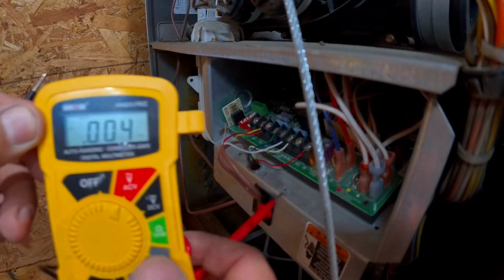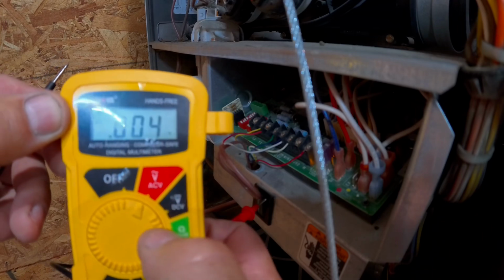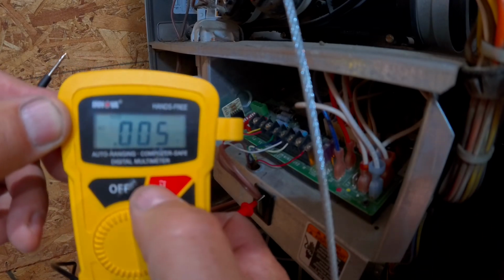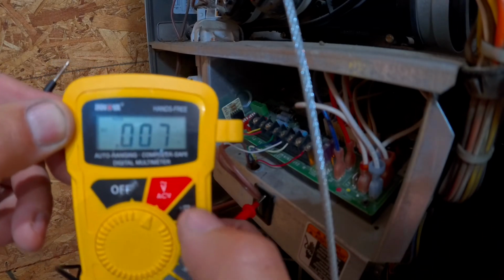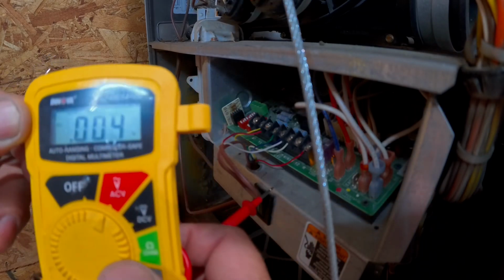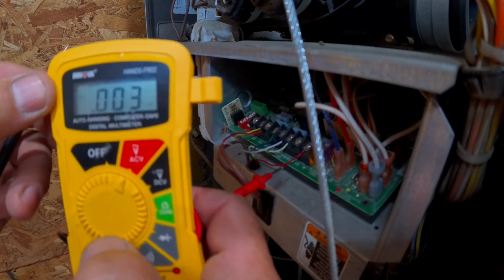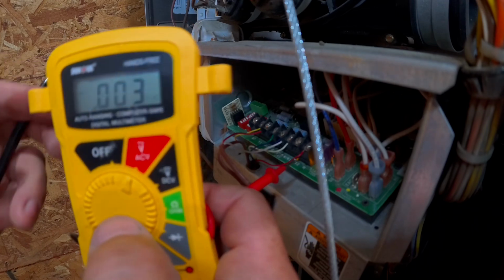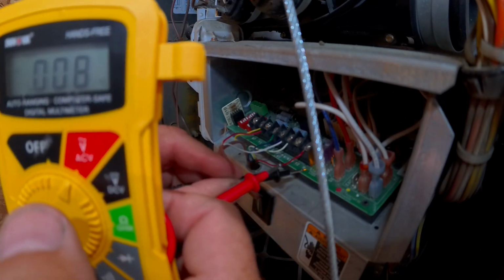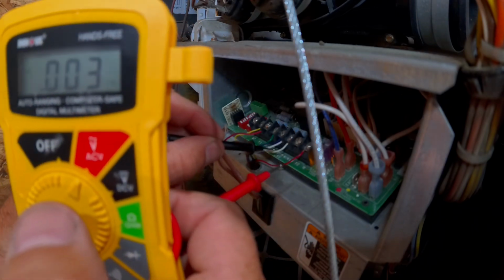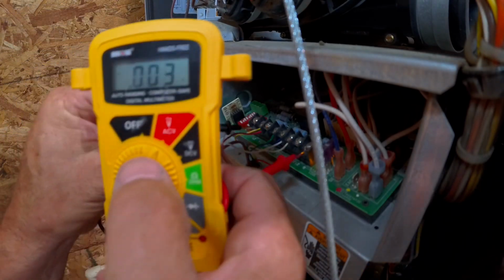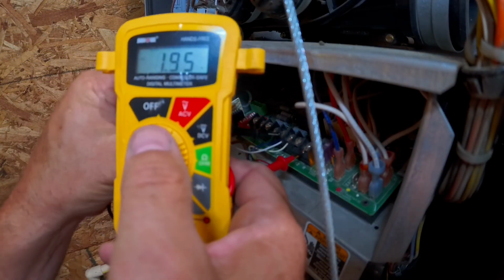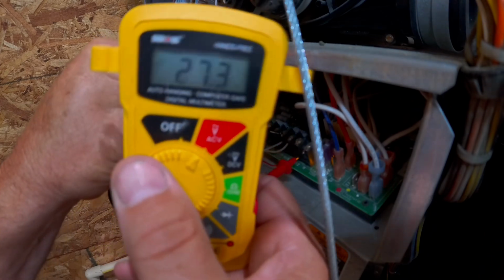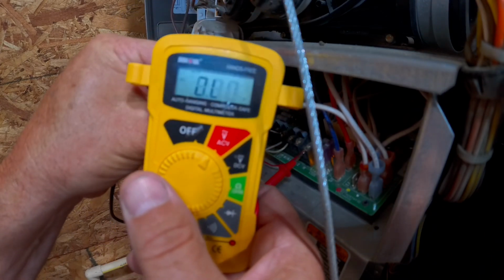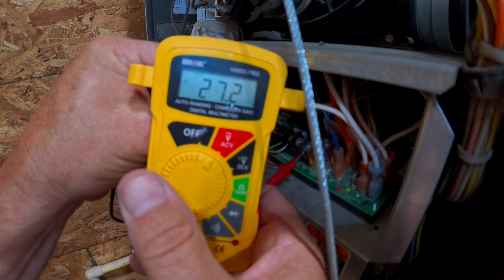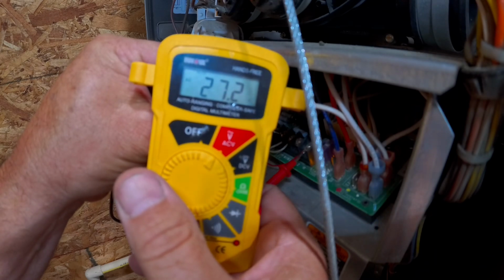So with our meter, we are set to AC voltage, ACV. You can see the V sign with the squiggly line above it. That means it's alternating current, which is AC voltage. So what we're going to do is check to make sure our transformer is in fact working correctly. We're going to check power from the R terminal to the C or common terminal, depending on how it's labeled in your furnace. So we're going to put the red one on the R, the black one on common, and we're going to look for 27.2 volts. So that tells us that the transformer is in fact working.